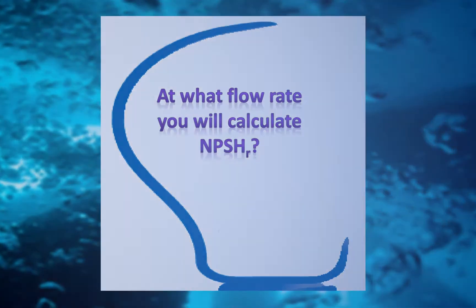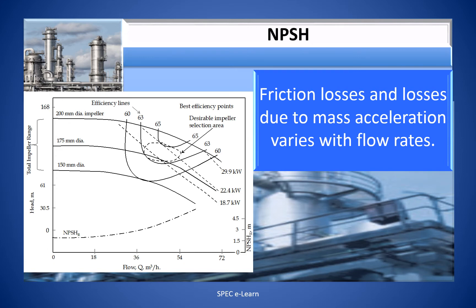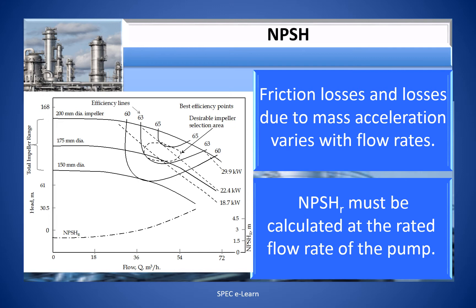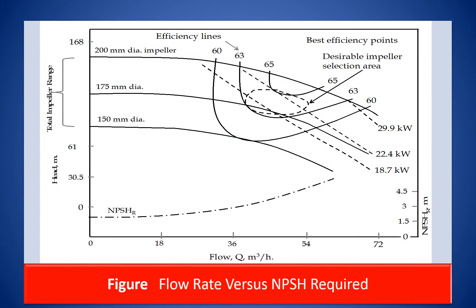At what flow rate should you calculate NPSH required? Friction losses and losses due to mass acceleration vary with flow rate. Since the pump is designed to run at the rated flow rate, NPSH required must be calculated at the rated flow rate. The NPSH variation with flow rate is illustrated in this figure. The line in red shows the relationship between NPSH required and volumetric flow rate — pump manufacturers supply this curve to customers. For example, the NPSH required at 50 cubic meters per hour is 4 meters.